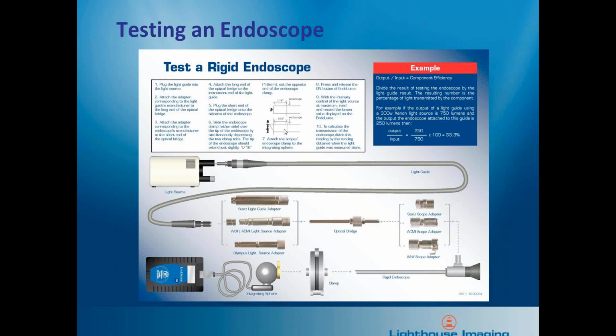And here in the upper portion of the laminated reference card, it shows you how to insert the tip of the scope into the clamp. Because we use the integrating sphere, it's really not that sensitive to this alignment, but the key to note is that the tip of the endoscope should project just a millimeter or two into the integrating sphere. If it goes a little bit deeper, it won't make very much of a difference, but if it's recessed a little bit, then you'll lose light into the clamp. So you should follow this guide here.